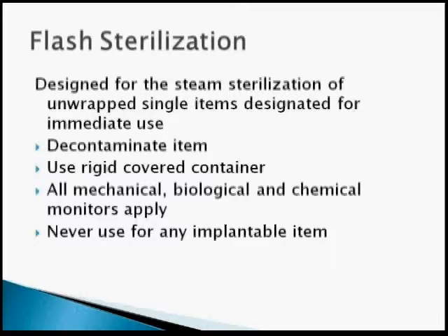You have to decontaminate the item. You have to use a rigid covered container for the flash sterilization. You just can't lay it in a pan. It has to be covered. And all mechanical, biological, and chemical monitors still apply. But you can never use these for an implantable item, okay? Because you really shouldn't release an implantable item until you know that your biological monitor is negative. And if you've got a true emergency situation, you can't wait to see if a biological monitor is negative. So there's a lot of caveats and restrictions placed on flash sterilization because it is a riskier way of sterilizing something.